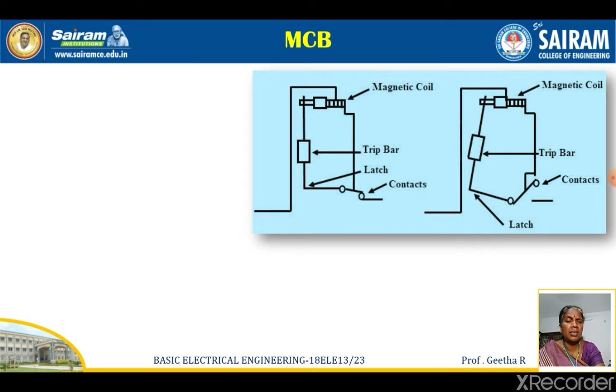So another way of operating is nothing but magnetic. Here during the short circuit conditions, the sudden rising of current causes the electromechanical displacement of the plunger associated with the tripping coil or solenoid of the MCB. See the magnetic coil connected to the circuit here.